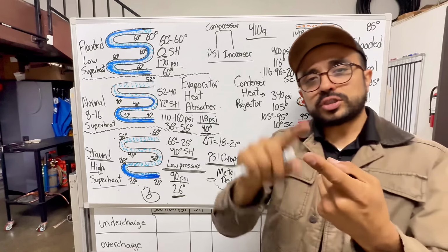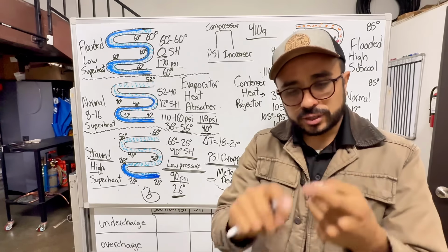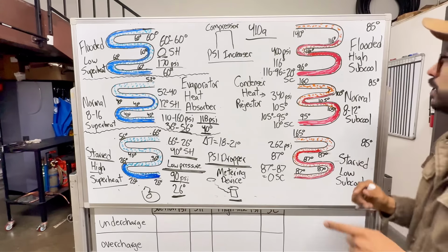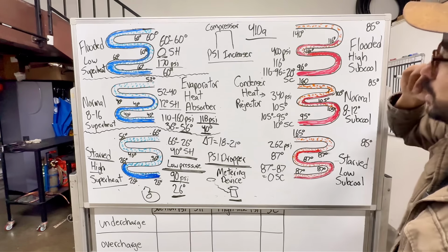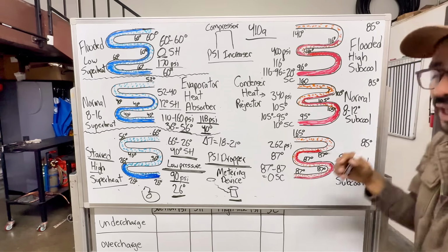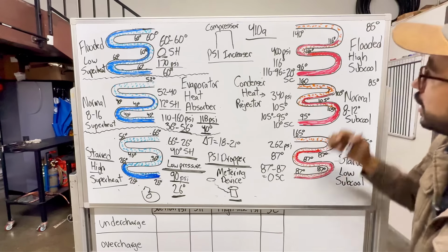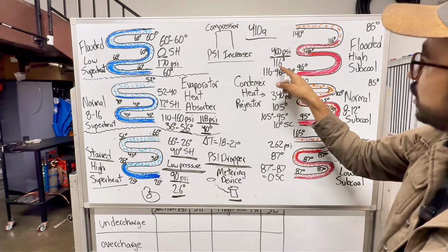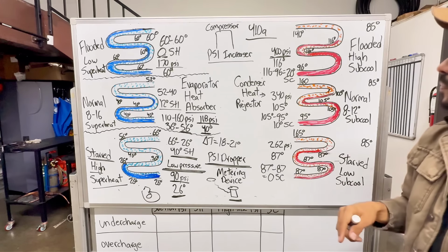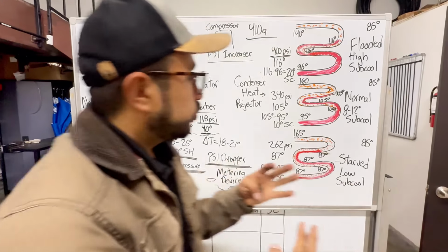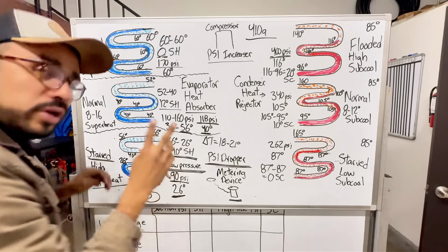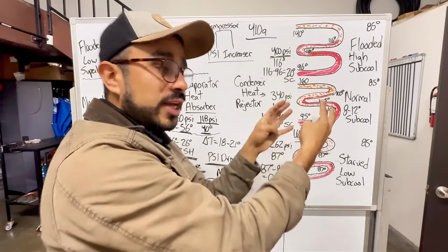The condensing temperature needs to be higher, right? Needs to be higher than your ambient air. That's the key, okay? So let's say a system that is flooded, meaning that it is overcharged, right? 410A, 400 psi, we have about 116-degree condensing temperature. Now, this is what's going on this side. This side, you only have 2 states, saturated and vapor. Right here, you have 3 states, vapor, saturated, and liquid.